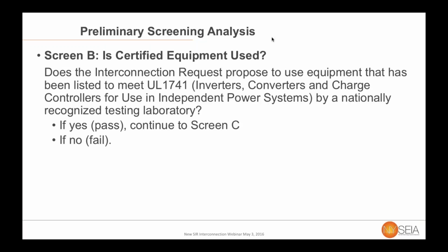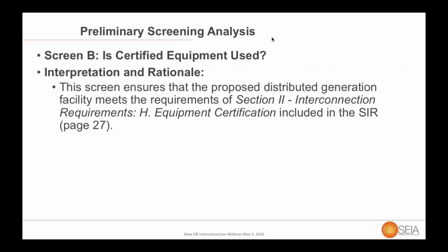So screen B, fairly simple screen. It simply asks, is certified equipment used? It asks, does the interconnection propose to use equipment that's been listed on the UL 1741 for inverters and tested by recognized laboratories? So if you are using certified equipment, then you pass this screen. So the rationale behind this is it implements essentially a requirement that is sitting within the SIR already and within the new SIR. So in addition to all of the technical screens that we're going to talk about, there is Section 2 of the SIR. It has been updated since its previous incarnations, but it still has a similar structure. And they're the overall design requirements for a system. And so several of the screens reference back to some of these requirements and are explicit tests to make sure that you are meeting this. So within Section 2 there, they have the requirement for equipment certification.